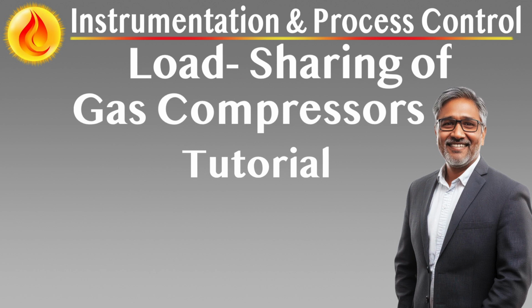Deviation-based surge risk estimation. The cold recycle controller evaluates a modified surge deviation DV using input from companion anti-surge controllers across the network. DV equals DV min times F of B times CRSO plus CRD, where DV min is the smallest worst-case surge deviation reported by any compressor. CRSO is a fixed bias introduced when surge conditions are imminent. CRD is a derivative response based on how fast the system is approaching surge. FB is a flow-based gain factor that adjusts sensitivity based on recycle rate. This equation ensures that the cold recycle control loop begins acting just before any single compressor reaches its own surge limit, providing a protective buffer and buying time for the system to stabilize.